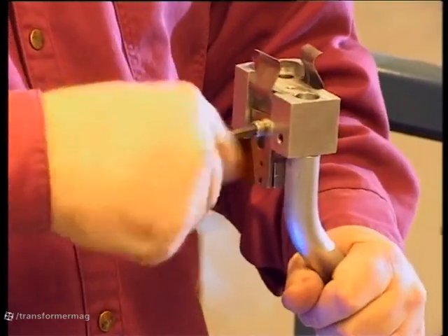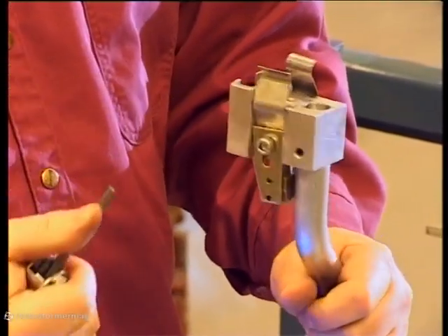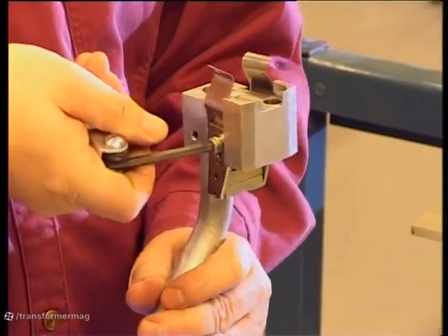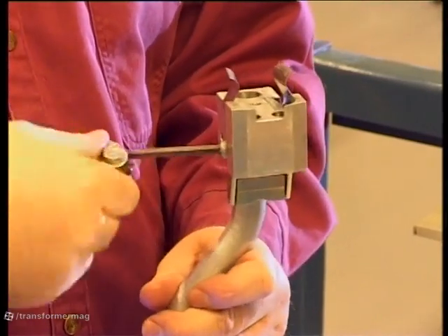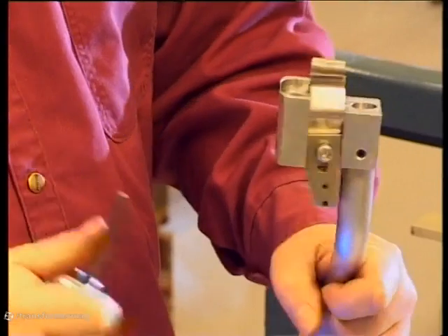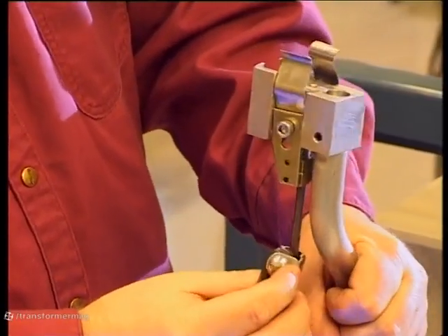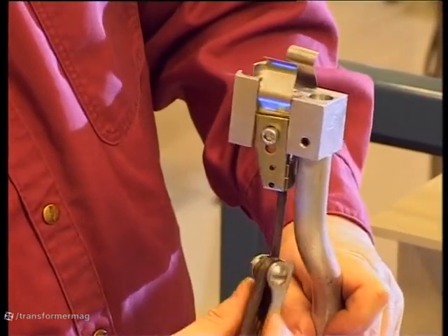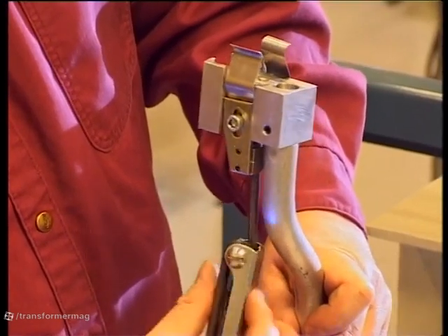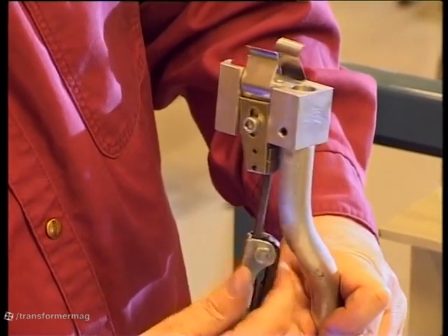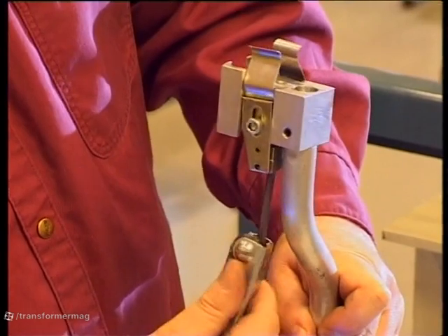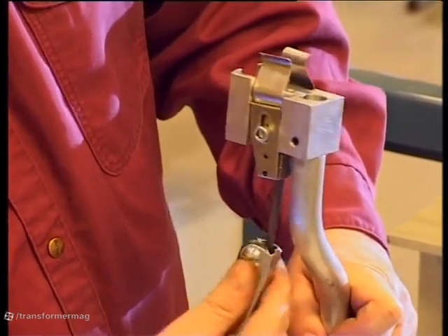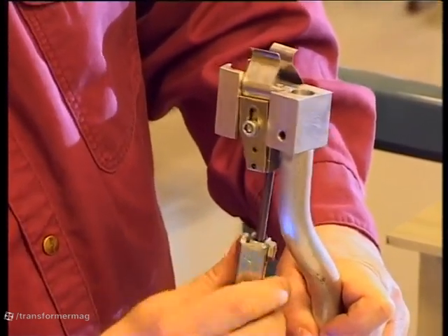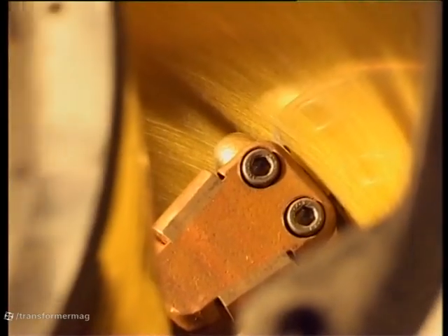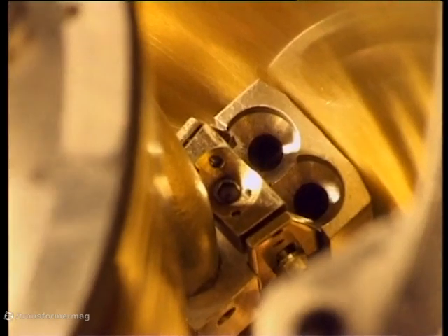Before removing contact blades, adjust the tool. The maintenance guide explains which contact blades to remove and how many of them. Before adjusting the contact holders of the holding tool, you must consult the maintenance guide to find out which pitch applies to your tap changer. Refer to section 363. Attach the holding tool to the contact blade of the first phase.